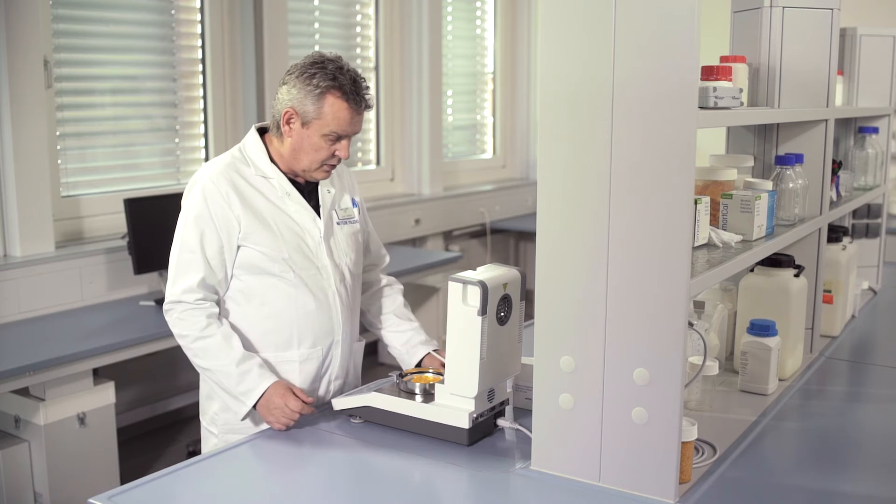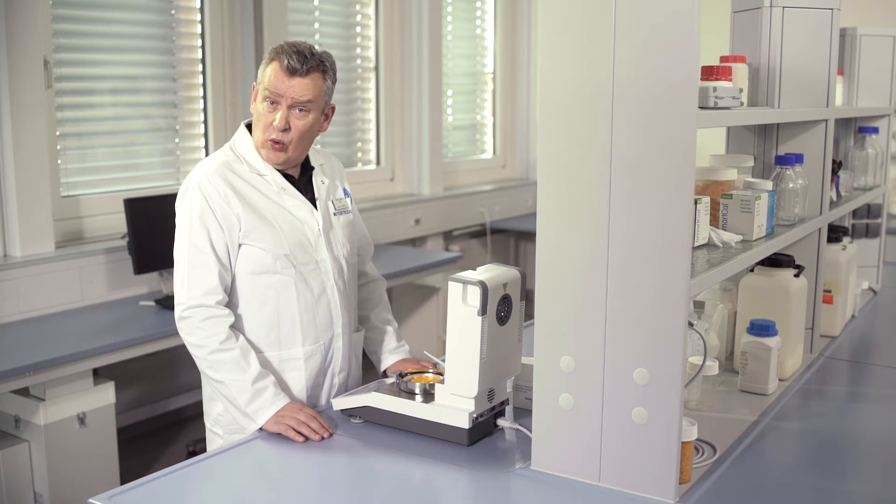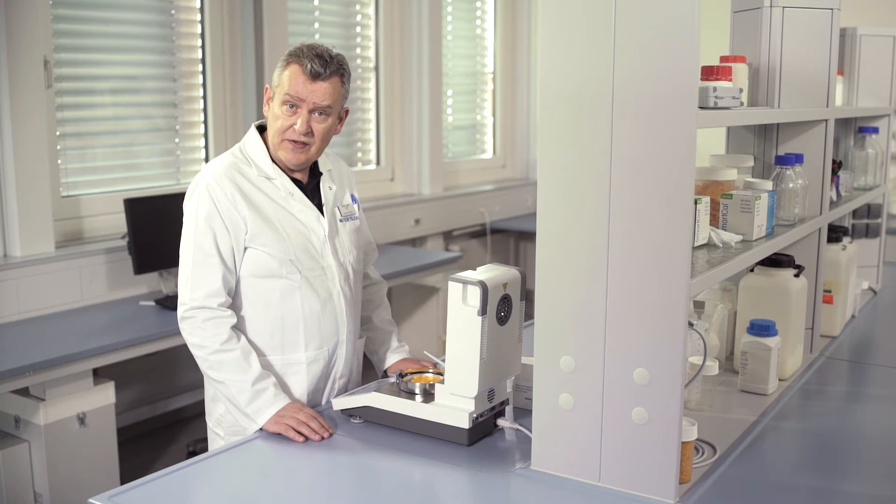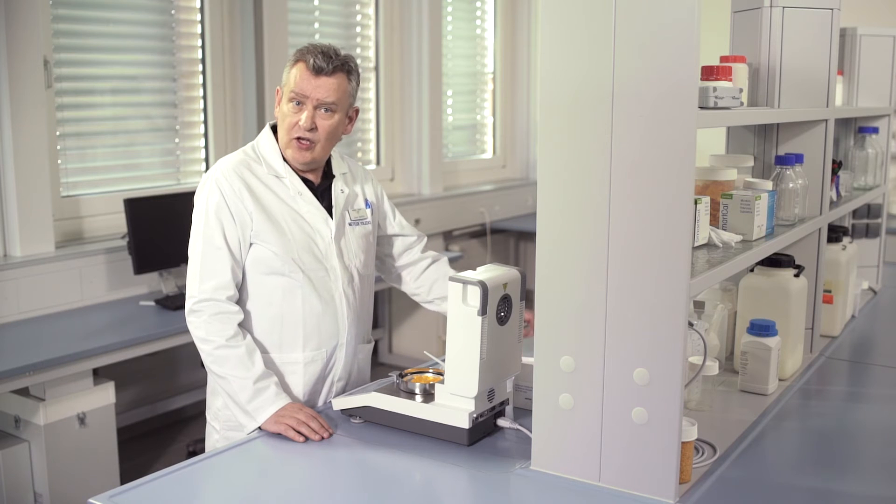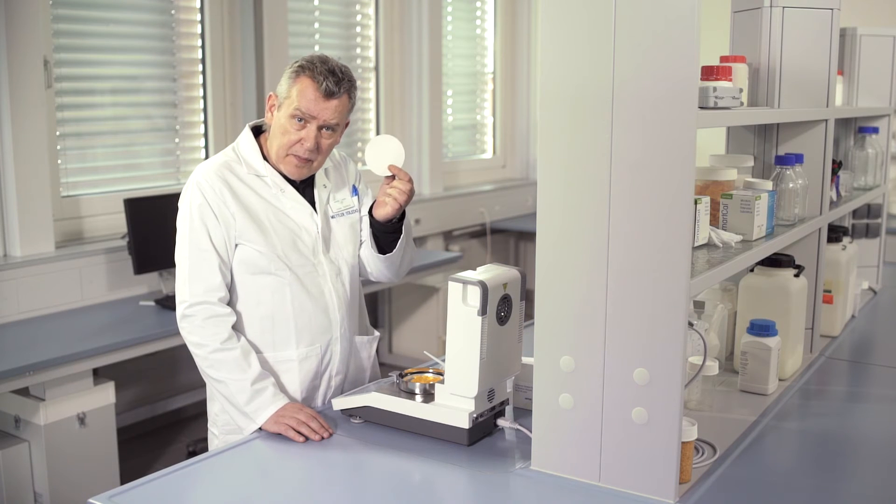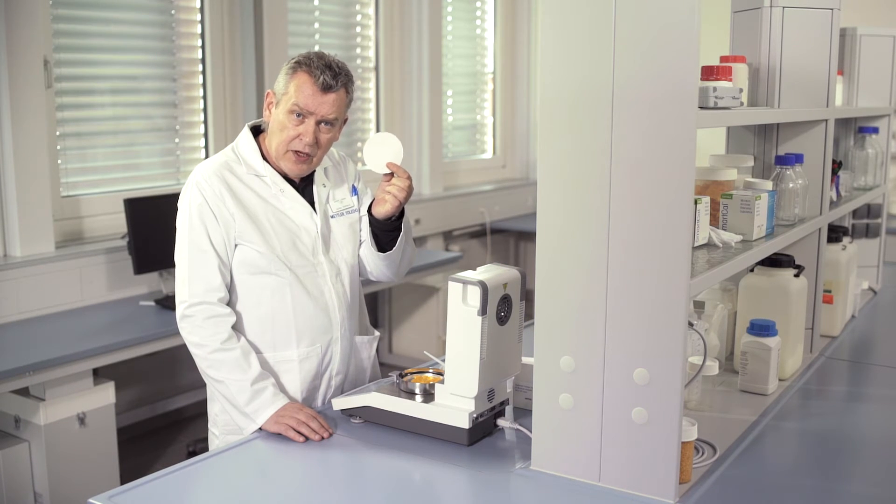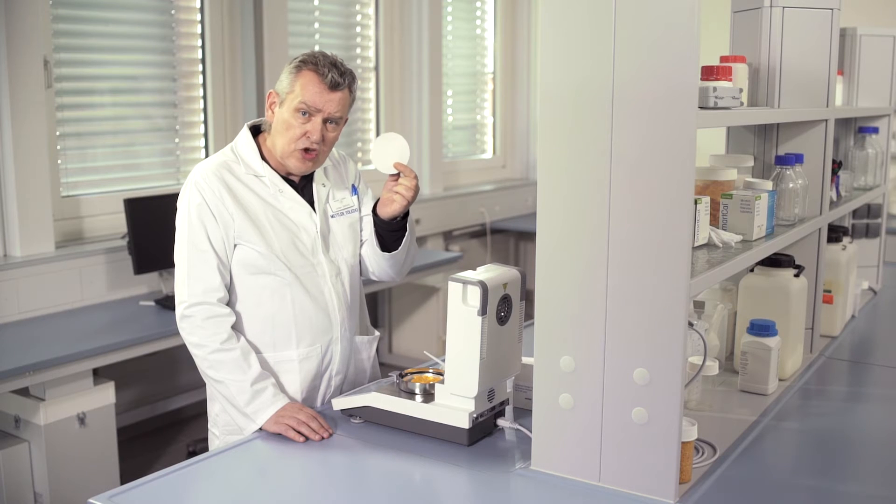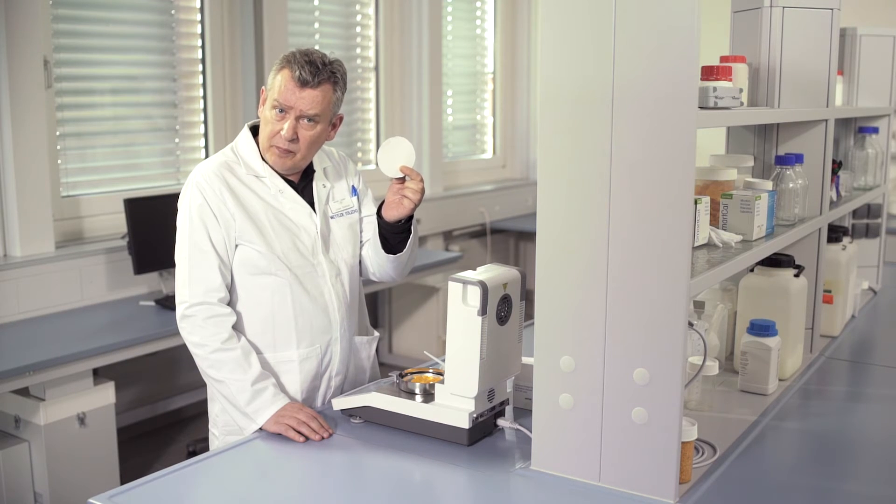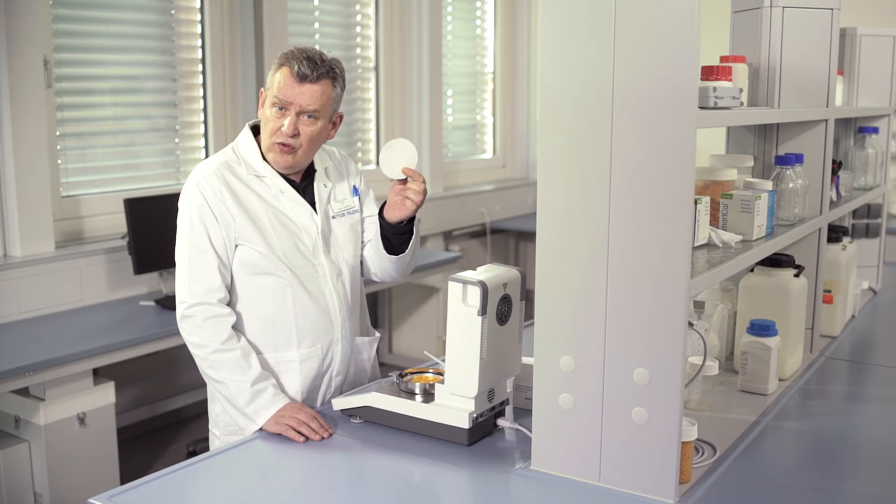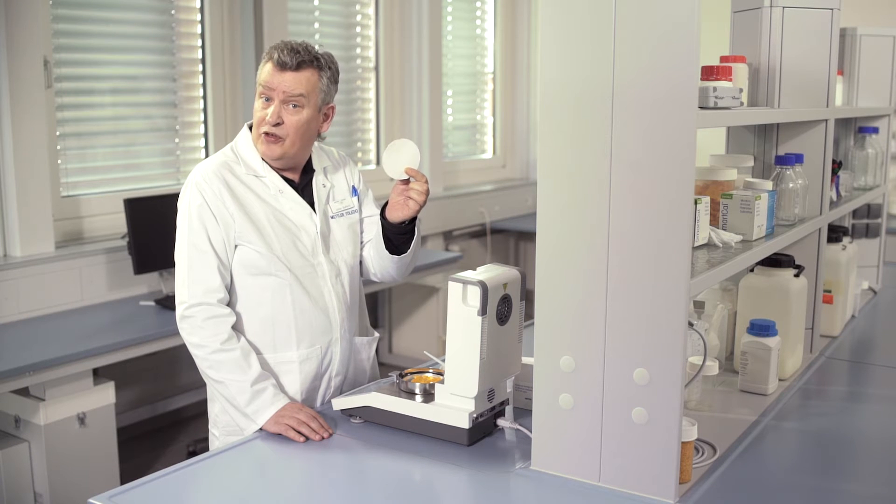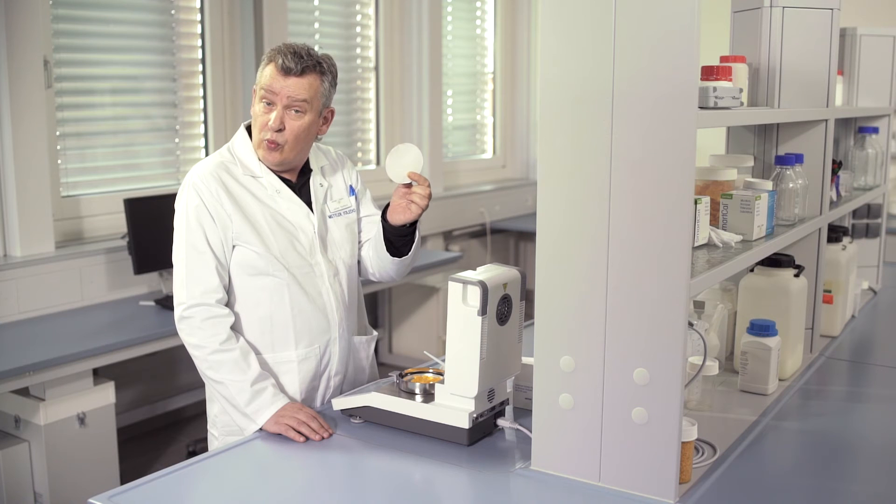For measuring liquids or pasty substances, we recommend using these glass fiber filter papers. A filter paper ensures fast and homogenous spreading of the sample and therefore reduces measurement time by up to 50 percent, as well as increasing repeatability.